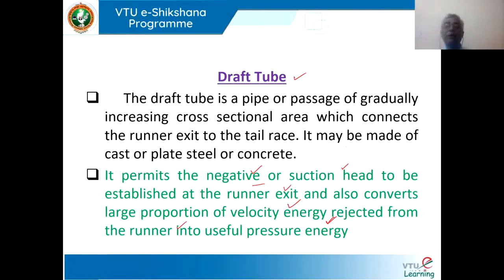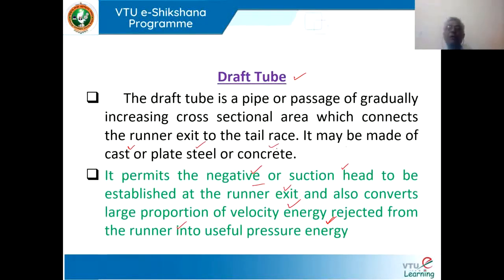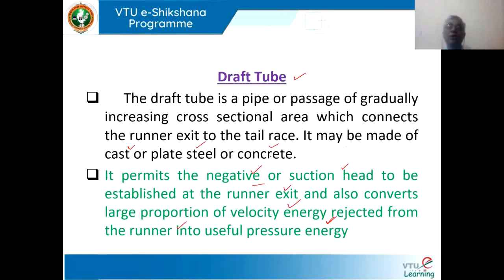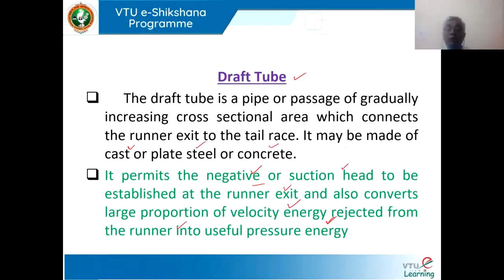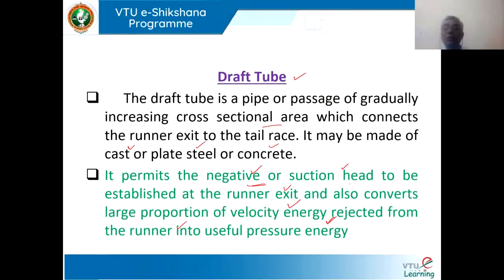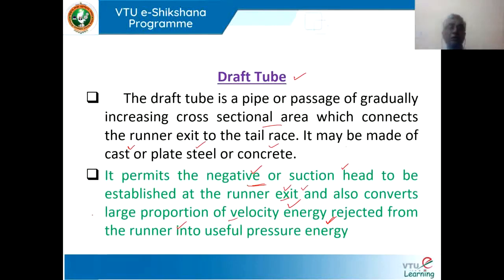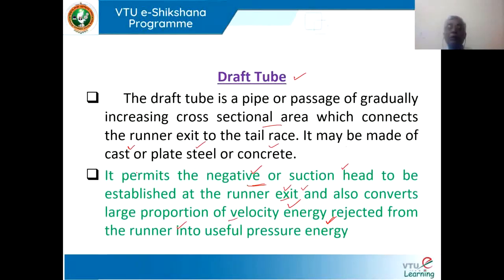The draft tube is made of cast steel, plate steel, or concrete. For very large Kaplan turbines, a concrete draft tube may be used; for very small Kaplan turbines, cast iron or plate steel draft tubes are used. It is a gradually increasing cross-sectional area pipe. Its purposes are: first, it permits a negative or suction head to be established at the runner exit; second, it converts a large proportion of velocity energy rejected from the runner into useful pressure energy. The draft tube theory will be discussed later.